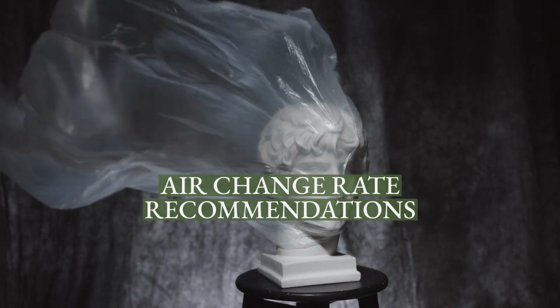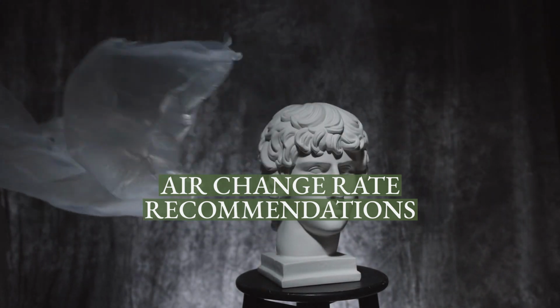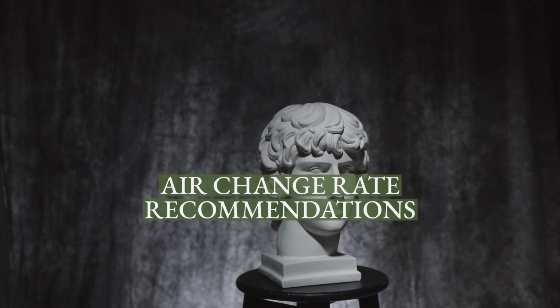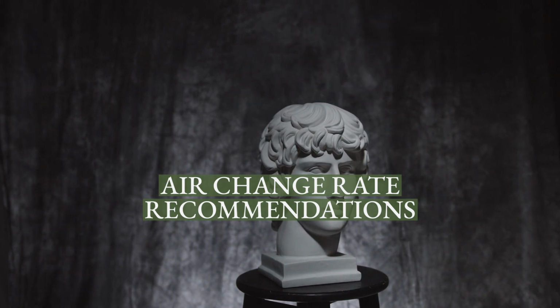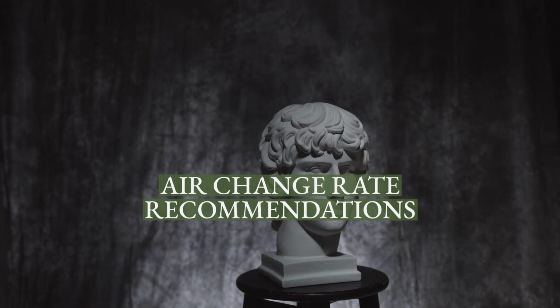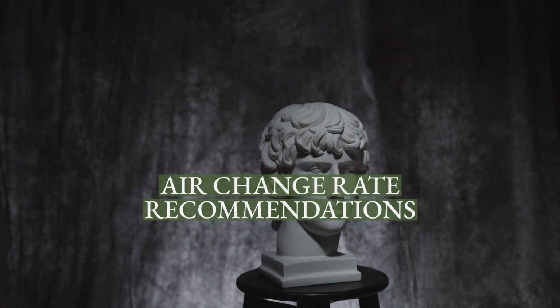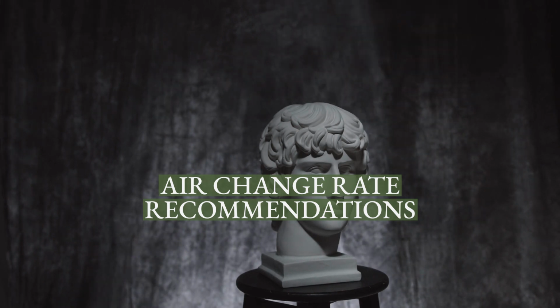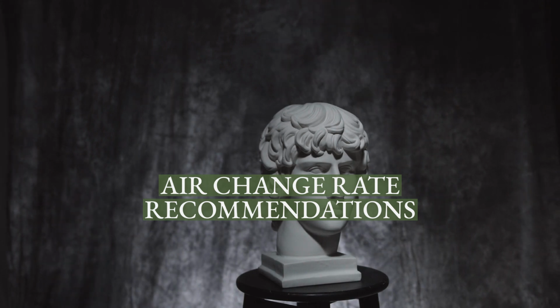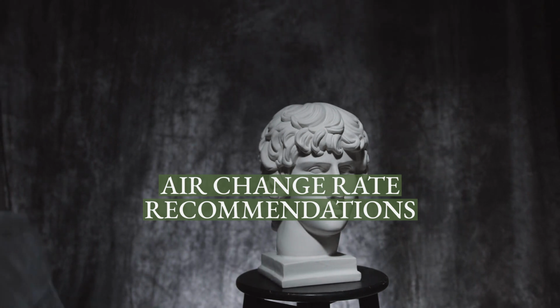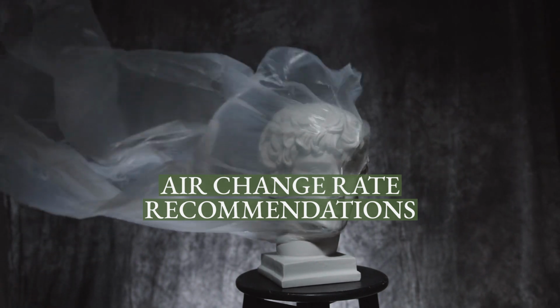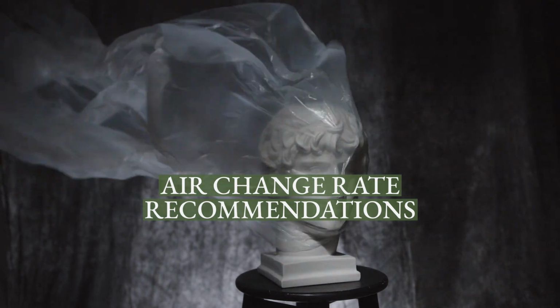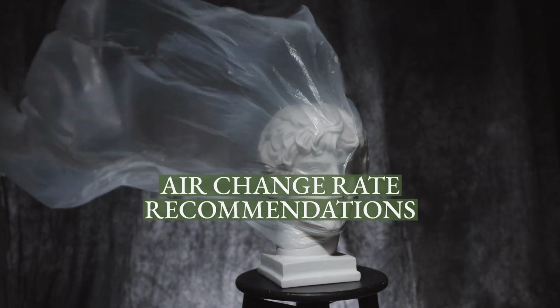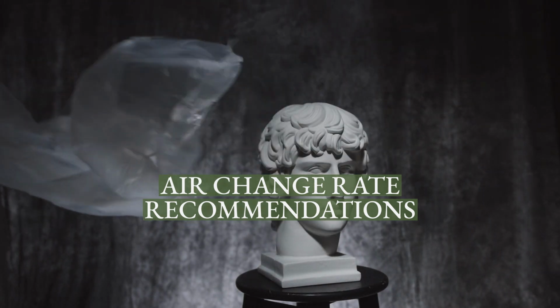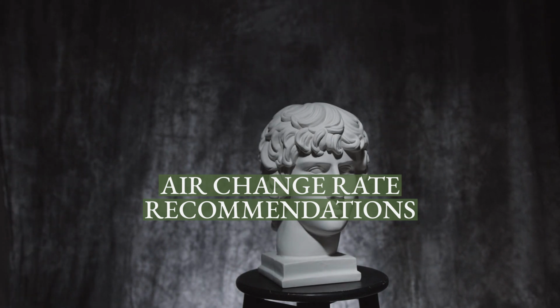Moving forward, we'll be taking a closer look at air change rate recommendations. Air change rates are often used as rules of thumb in ventilation design. However, they are seldom used as the actual basis of design or calculation. For example, residential ventilation rates are calculated based on area of the residence and number of occupants. Non-residential ventilation rates are based on floor area and number of occupants, or a calculated dilution of known contaminants. Hospital design standards use air changes per hour. Recommended air change rates can be found in relevant standards.